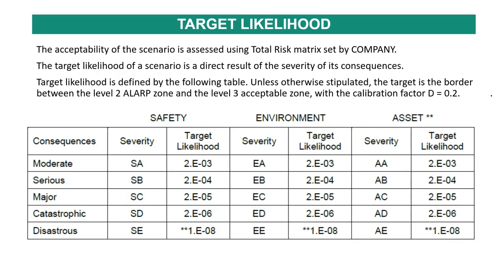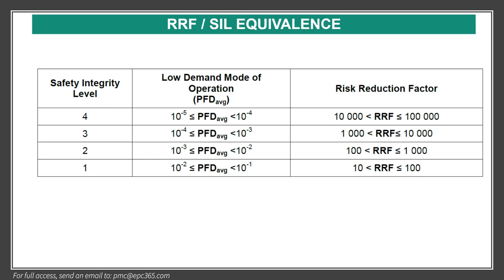The calculated likelihood equals the initiating event likelihood multiplied by the time at risk, the exposure parameter, and the probability of failure on demand. When you have the calculated risk, you compare it with the target likelihood. For example, for a safety disaster scenario, your target should be 1×10⁻⁸. SIL 1 corresponds to a risk reduction factor between 10 and 100, where the PFD is between 10⁻¹ and 10⁻².